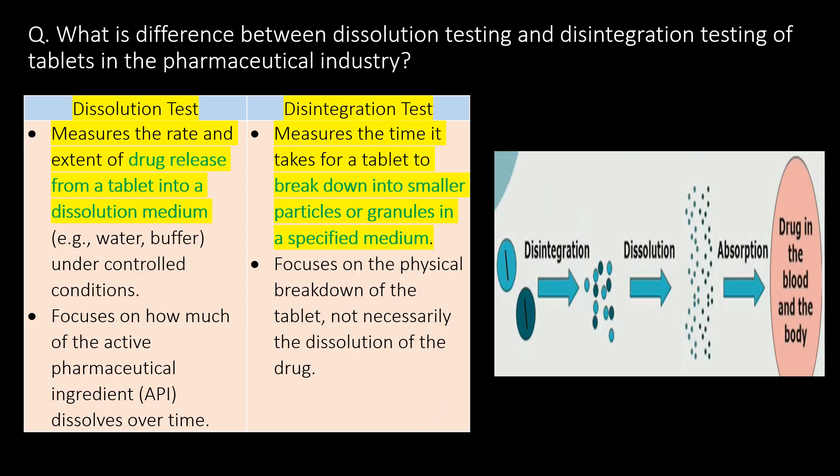A very frequently asked question: what is the difference between dissolution testing and disintegration testing of tablets in the pharmaceutical industry? Dissolution test measures the rate and extent of drug release from the tablet into a dissolution medium, whereas disintegration test measures the time it takes for tablets to break down into smaller particles or granules in a specified medium.